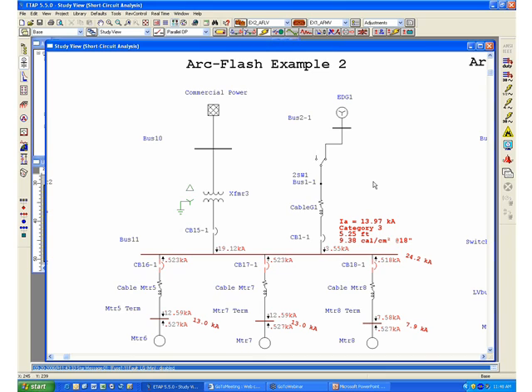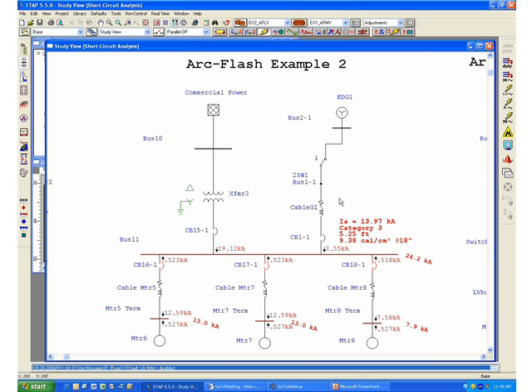In this case now, we have a category 3 with about 9.38 calories per centimeter squared. This is most likely caused by the contribution of the utility and the generator at the same time, and we have an increase in the amount of arcing current while we still maintain the constant full clearing time response from the low voltage circuit breakers in this system.